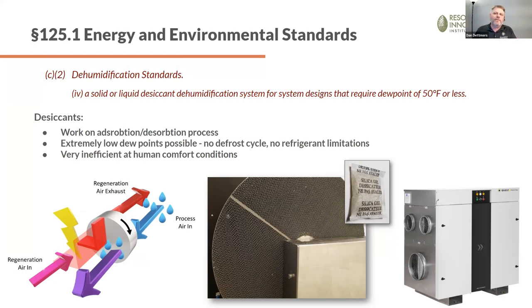But if you're one of those growers that wants to get down to a dew point of 30 or 25, or maybe even less, trying to get the hues to pop, the purples, the oranges, when you're stressing the plant the last couple of weeks, that's where a desiccant dehumidifier may be your only option. But make sure you have the actual requirement to get to a dew point of 50 degrees or less, and please try to have some other option for dehumidification for the rest of the time, or you're really going to pay for it throughout your entire growth cycle.